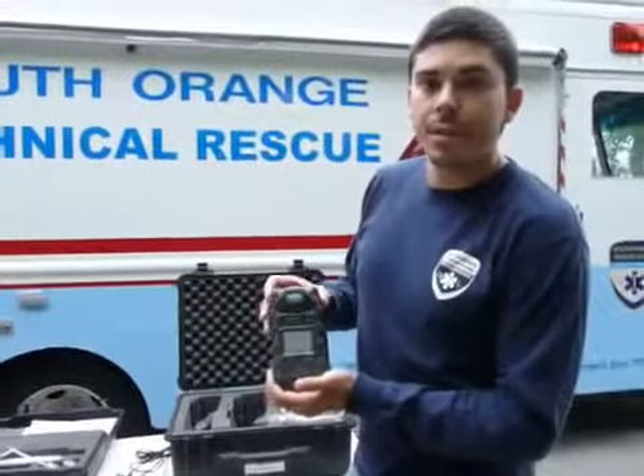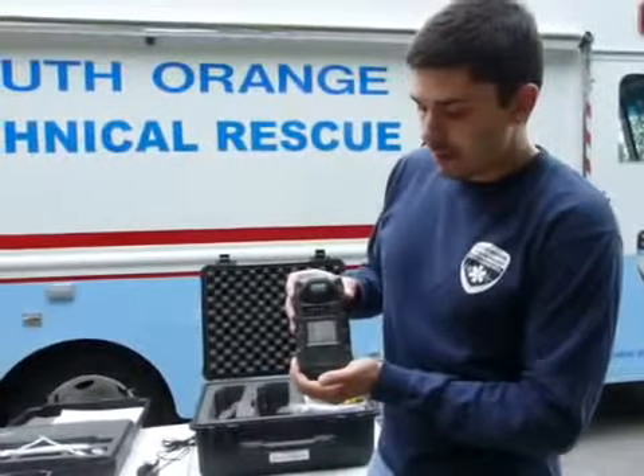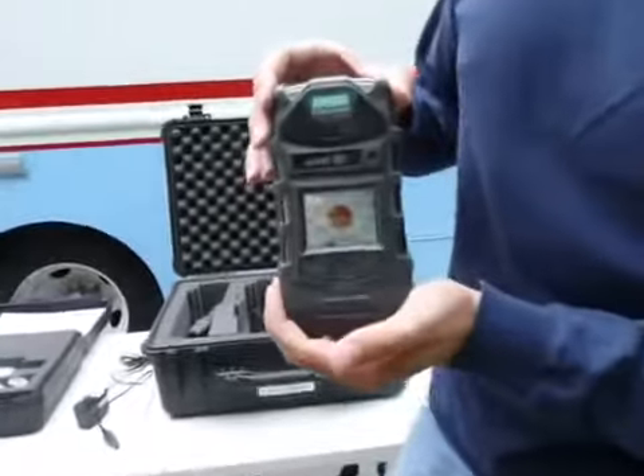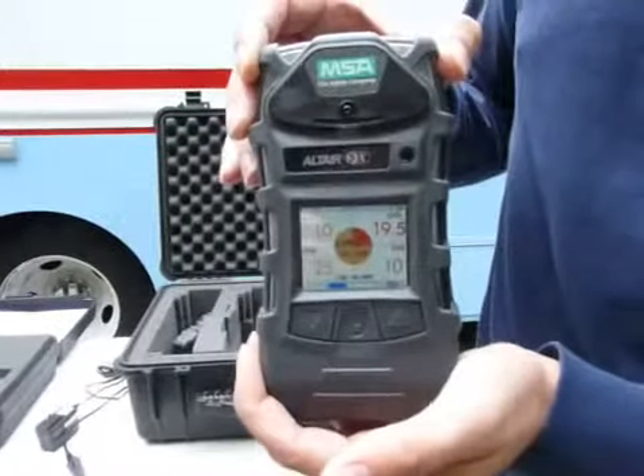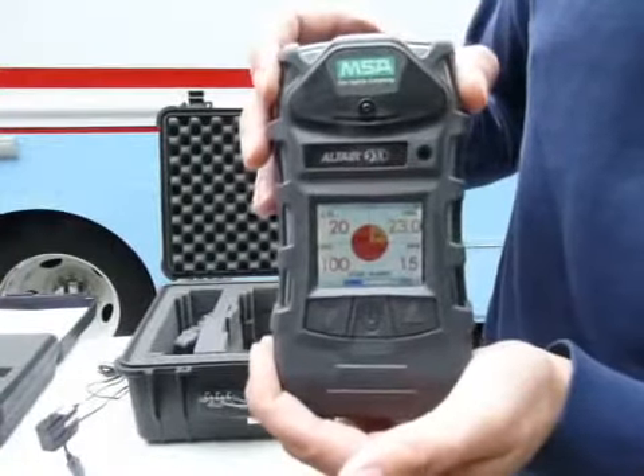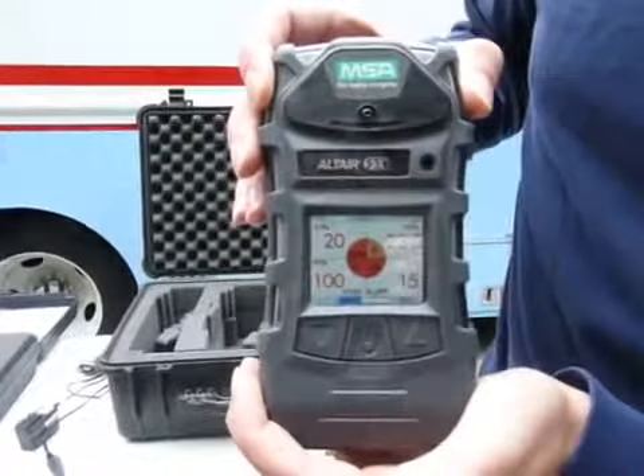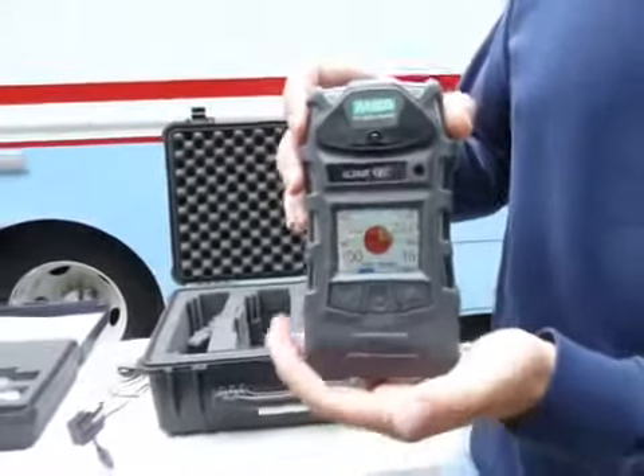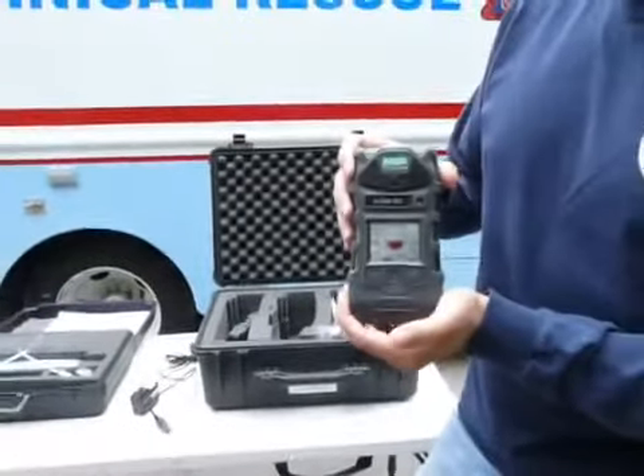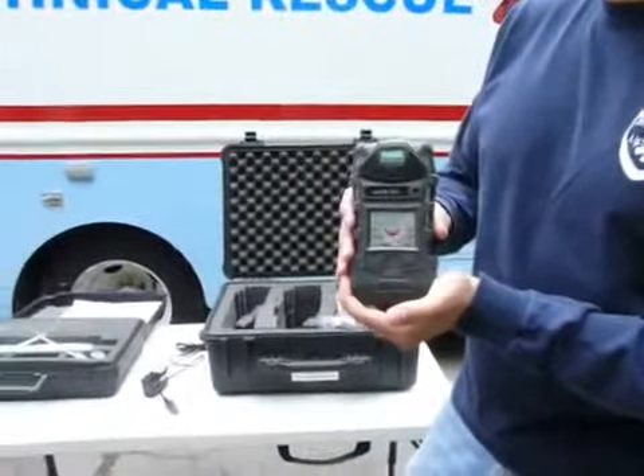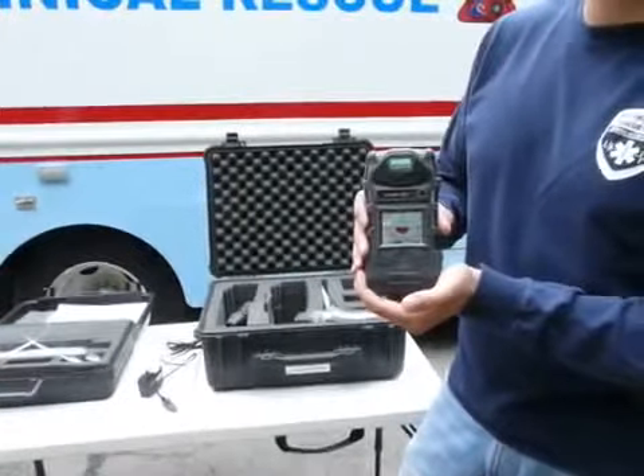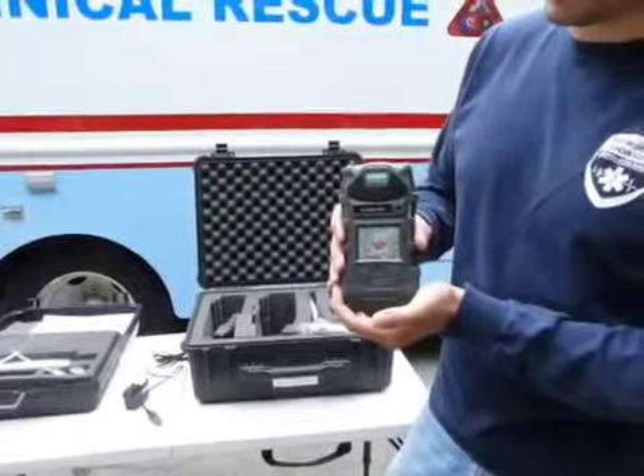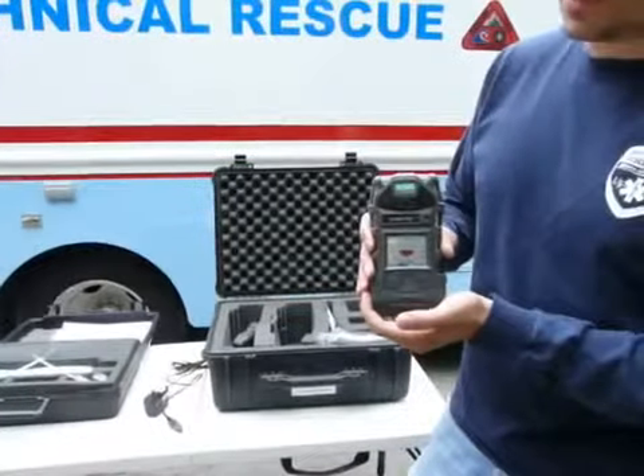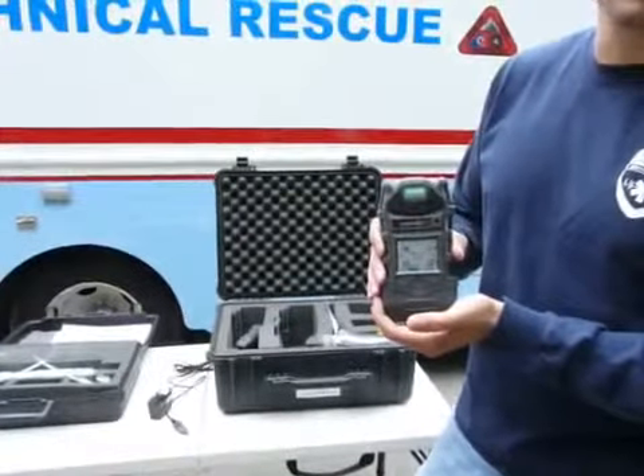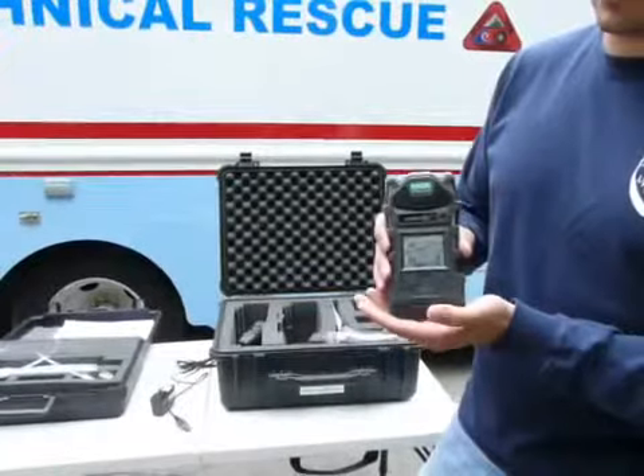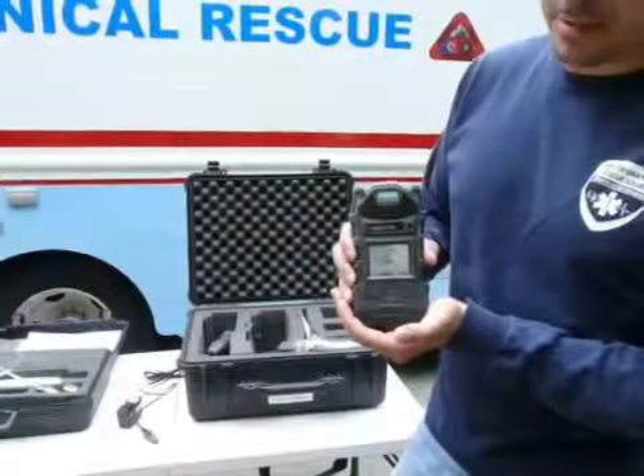Right now it's going through each of the different sensors. It's going to go through the oxygen sensor, then the combustible sensor, then the carbon monoxide sensor, and the hydrogen sulfide sensor, and it's going to give you the low and high levels for each of these that it's going to alarm at. This process takes a little bit of time, so you have to be patient. It's also why it's important to turn this unit on quickly when we get on scene, so that it can go through this orientation startup process before we need to use it.